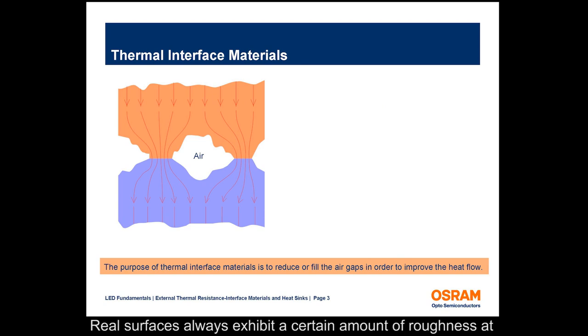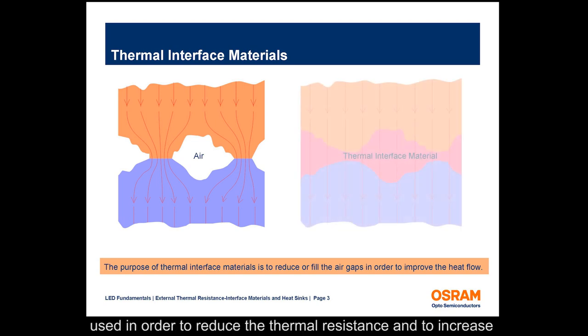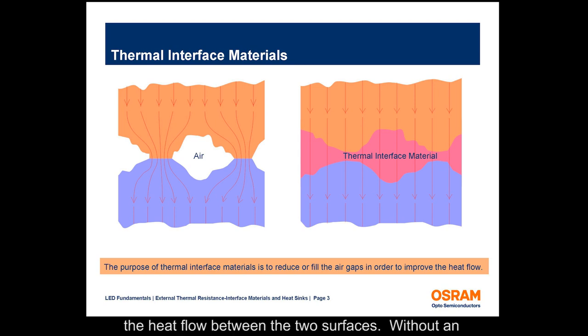Real surfaces always exhibit a certain amount of roughness at the micro level and are never perfectly smooth. Physical contact between two surfaces only occurs at isolated points, with air pockets in between these points. Since air is a poor conductor of heat, a more conductive material can be used to reduce the thermal resistance and increase the heat flow between the two surfaces.